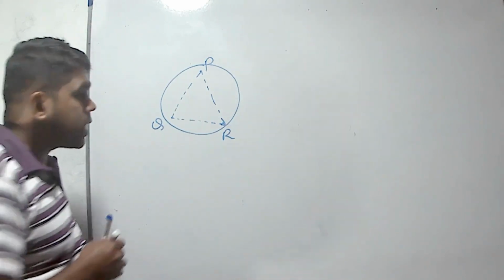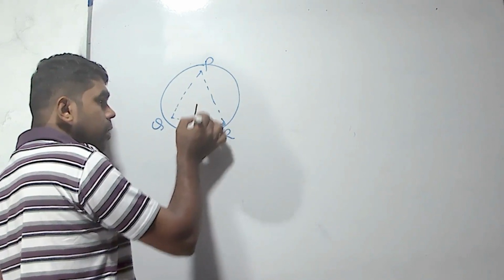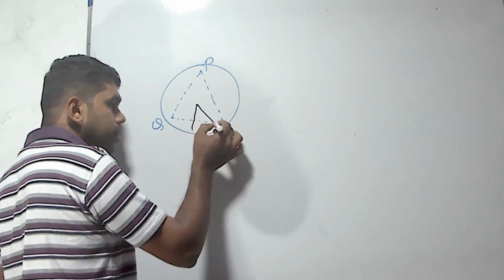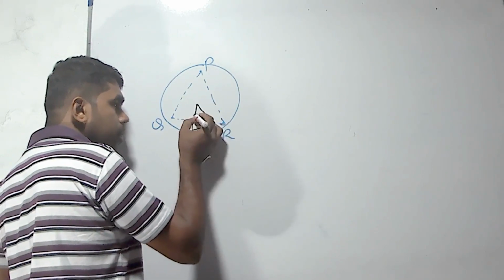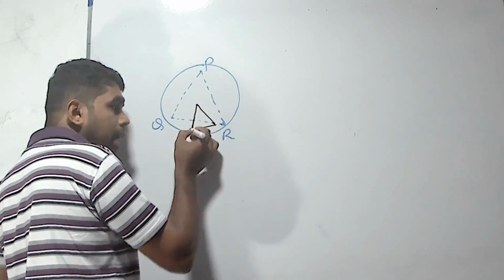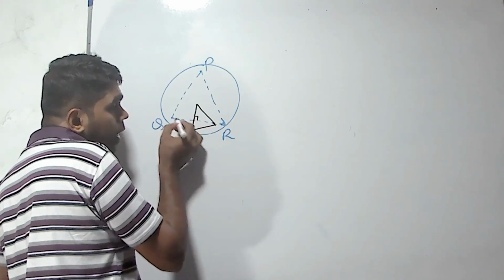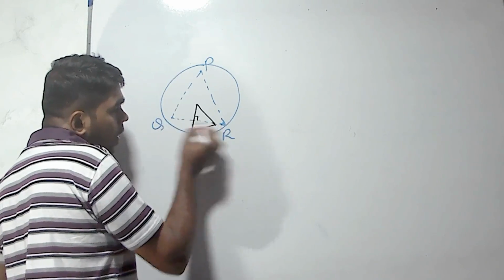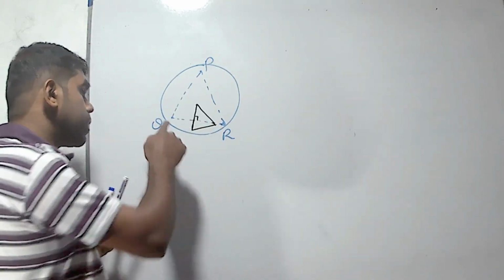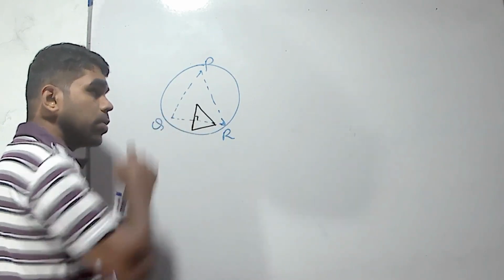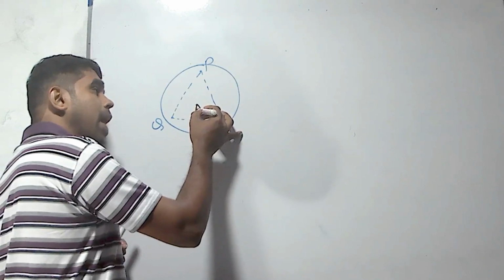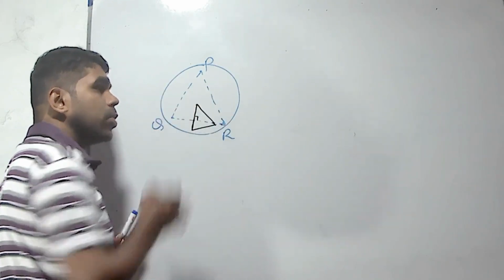Then we have to place the prism such that the side of the prism is perpendicular to a line joining 2 screws, and the prism angle should be placed near the center of the prism table.